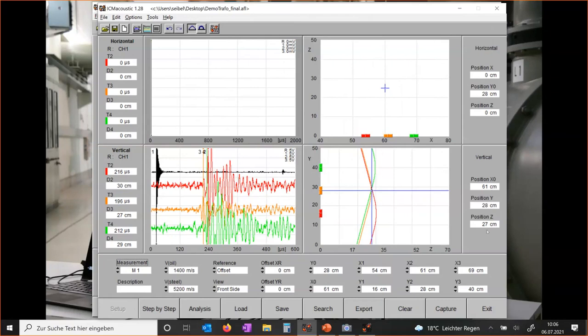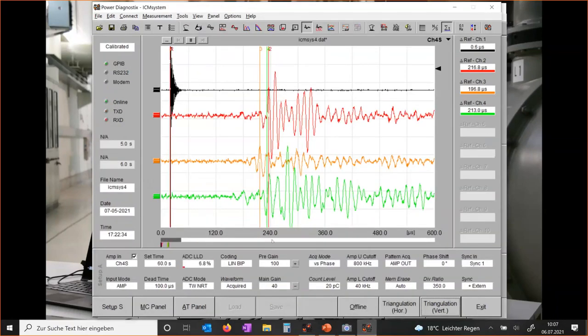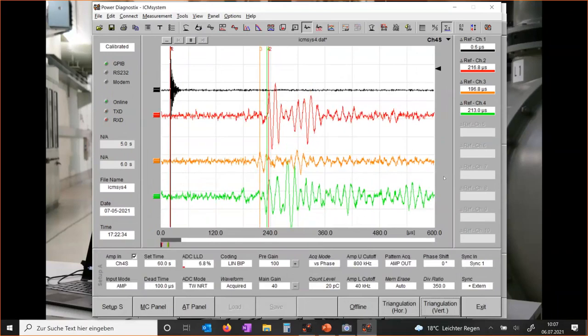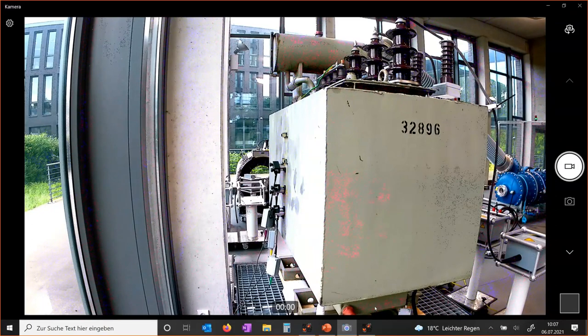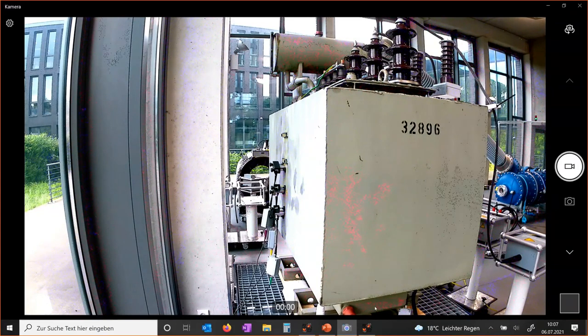This is the first position from the acoustic fault location. We need to verify this vertical detection result by performing the same step with a horizontal sensor arrangement. To do this, we switch off the voltage and rearrange the sensors.